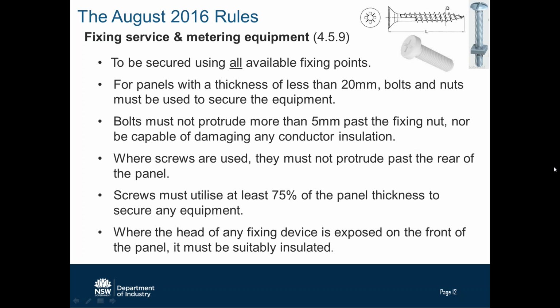They must not protrude past the back of the panel, and they must use at least 75% of the panel thickness. So for a 25 millimetre panel, you've got to use screws that penetrate, say, 19 or 20 millimetres, for example. The rules used to specify steel bolts. You can now use nylon nuts and bolts, for example, and that will help you because on the front of the panel, the heads of the screws or bolts have to be suitably insulated.